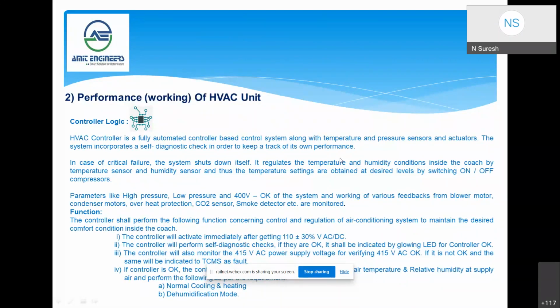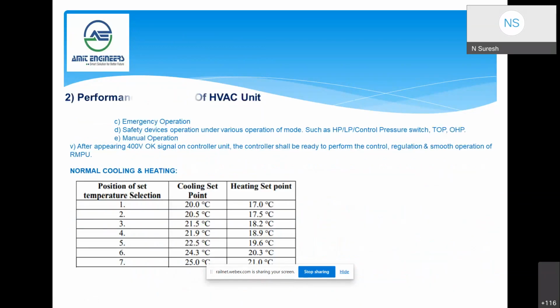This is about the control logic. What are the sequences the controller will check before it starts working? The controller shall perform the following functions concerning control and regulation of the air conditioning system to maintain the desired comfort condition inside the coach. The controller will activate immediately after getting 110 volt DC and perform a self-diagnostic check. If they are okay, it shall be indicated by a glowing LED for controller okay. The controller will also monitor the 415 volt AC power supply. If it is not okay, the same will be indicated to TCMS as a fault. These are the cooling and heating set points.